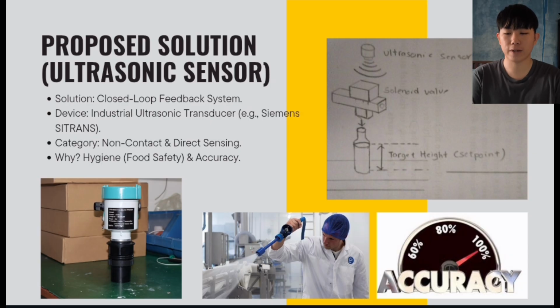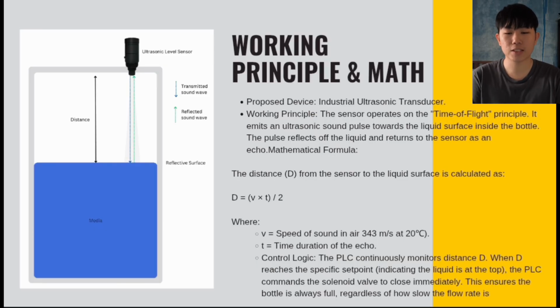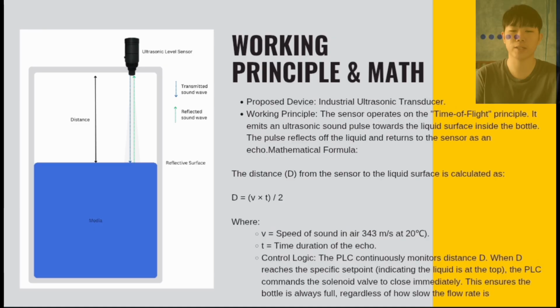And now we move on to slide 5, working principle. The device works on the time of flight principle. The sensor emits an ultrasonic pulse towards the liquid. This pulse hits the surface and reflects back as an echo. We calculate the distance d using the formula d equals v times t over 2, where v is the speed of sound. The PLC continuously monitors this distance. As soon as the liquid reaches the set point, the PLC commands the valve to close immediately. This ensures the bottle is full regardless of how slow the water is flowing.